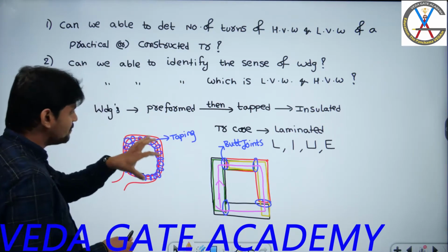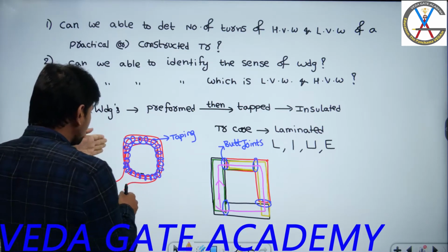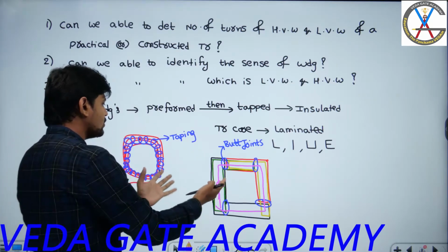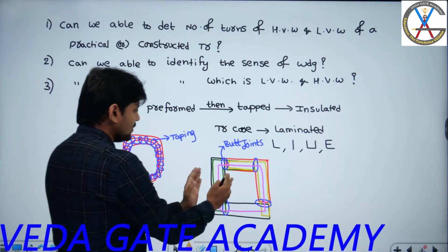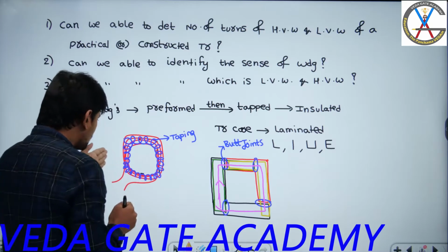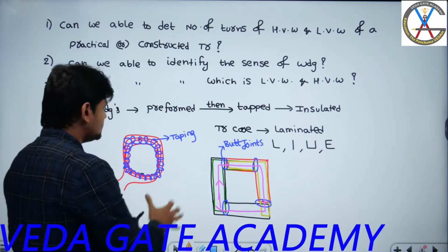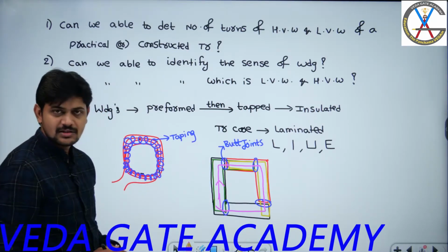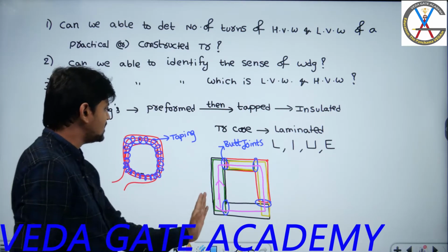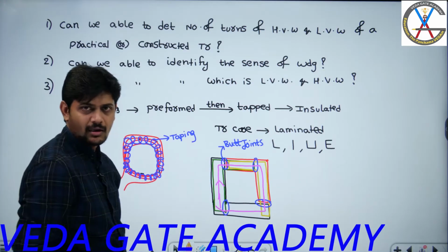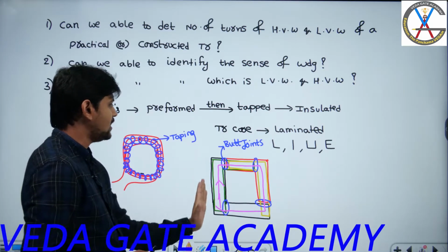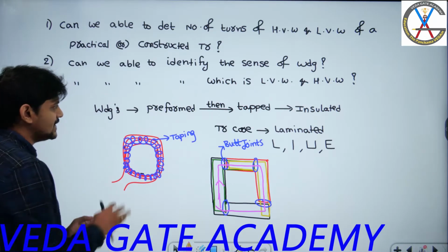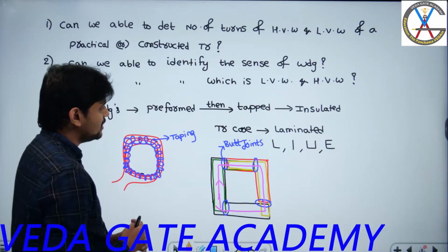Now what I will do is, this is the structure, right? So here, after the winding is preformed, around this winding I will place one L shape, and in this side an L shape. Likewise, totally I am going to get around this winding. If you imagine, you will get it over here. I am going to place L-shaped magnetic plates around this. Similarly, one more winding, with L-shaped magnetic plates in this. So I am going to get the final structure in this fashion. It is very easy for us to insert a straight L-shaped magnetic plate, right? Are you following what I am saying? This is L-shaped straight, and anyway this one comes. So this is the practical way of designing windings as well as the transformer core, right?